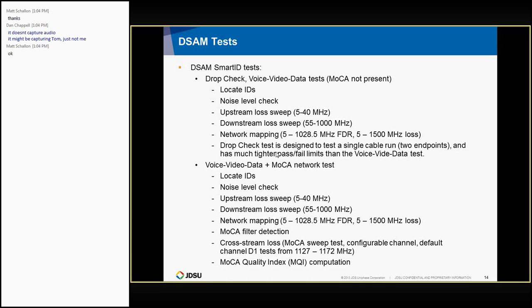The tests are essentially identical, except the drop test is designed for a single cable run with 2 endpoints and has much tighter pass-fail limits than the other. The voice video data plus MoCA is the same as what I just described, but also includes a cross-stream sweep test between all of the MoCA endpoints to test for loss between the endpoints, for MoCA traffic. And they have a bunch of different channels that you can be operating on. There's a default channel of D1 that tests from 1127 to 1172. I know MoCA runs over potentially anywhere from as low as somewhere around 500 megahertz to up around 1650 megahertz, thereabouts, depending on which version of MoCA you're using and which channels you're using.